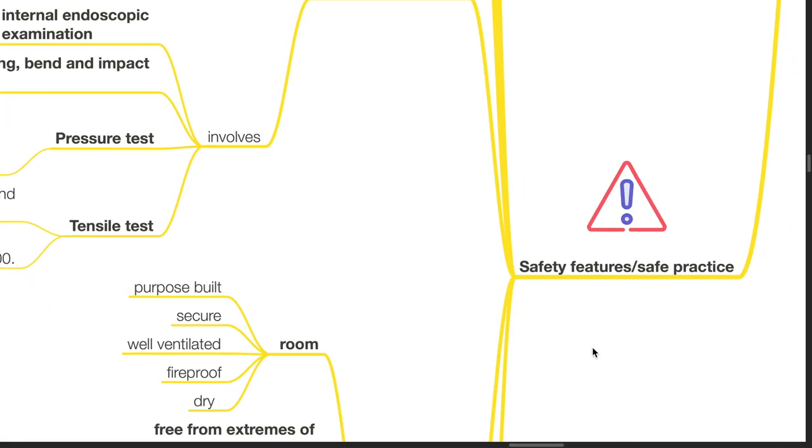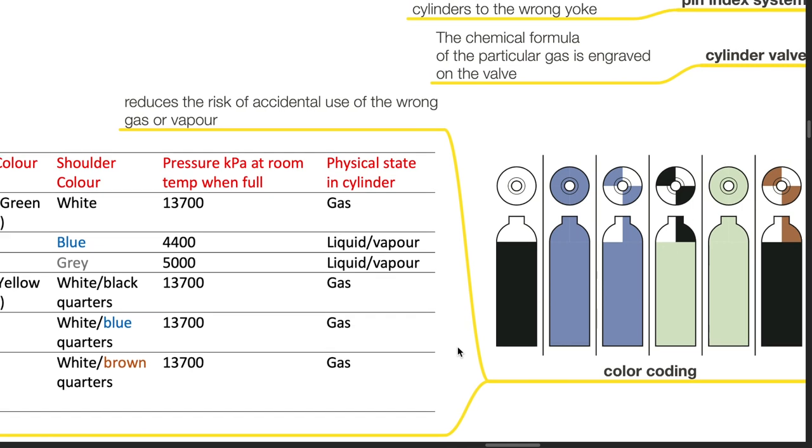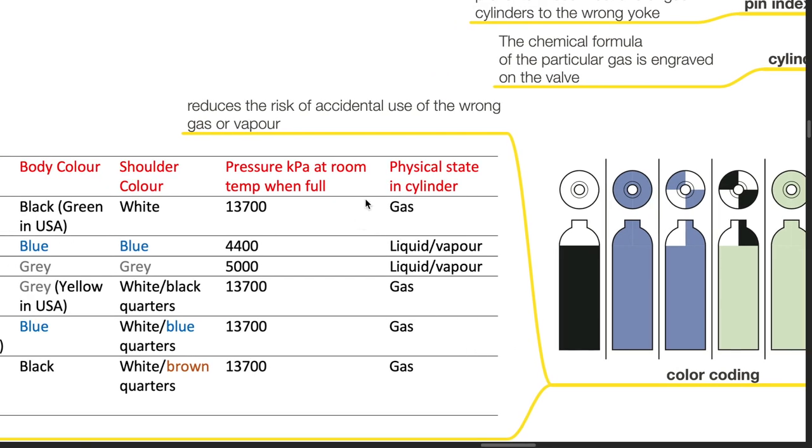Safety features and safe practice: Gases and vapors should be free of water vapour when stored in cylinders. Water vapour freezes and blocks the exit port when the temperature decreases as the cylinder is open. Pin index system, as mentioned, prevents misconnections of gas cylinders to the wrong yoke. Cylinder valve: The chemical formula of the particular gas is engraved on the valve. Color coding of gas cylinders reduces the risk of accidental use of the wrong gas or vapour.